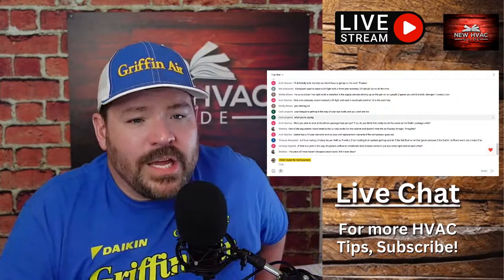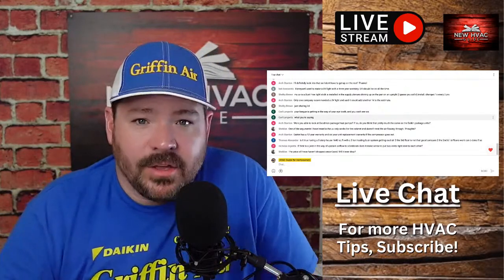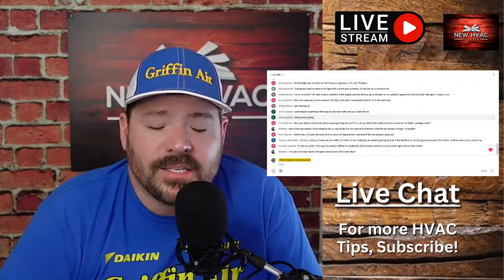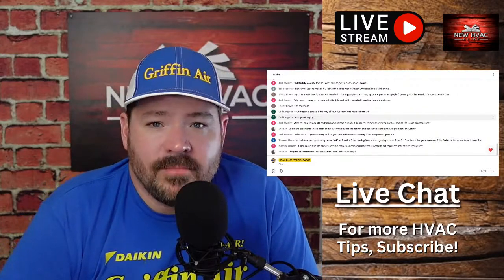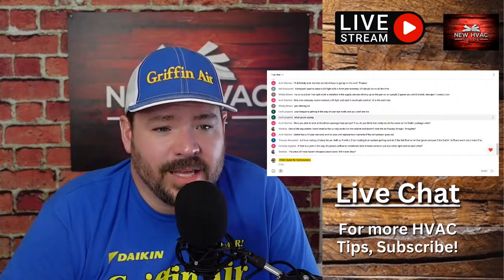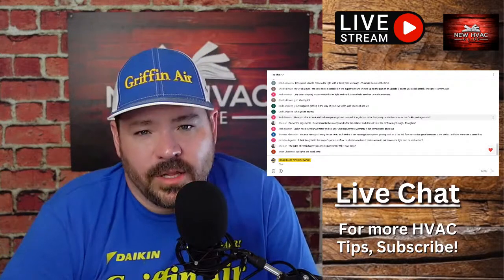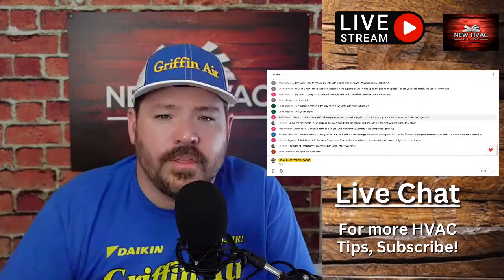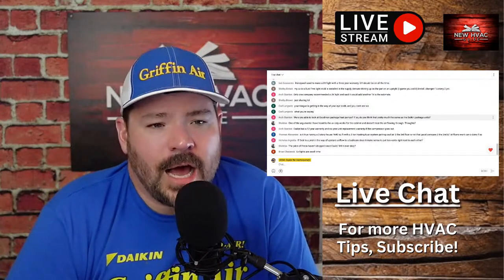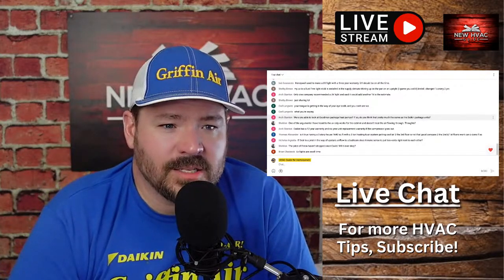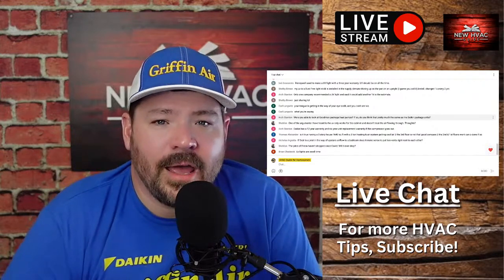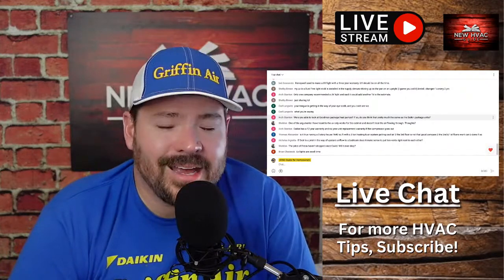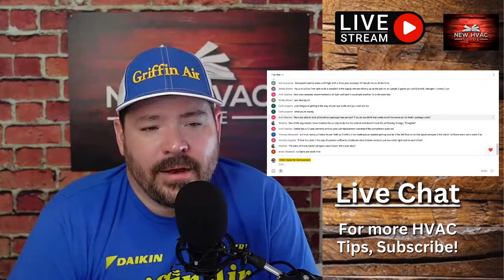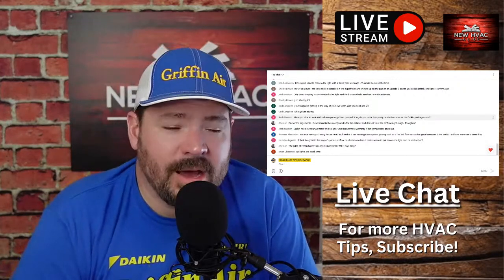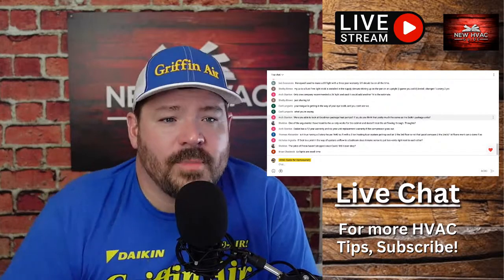So we talked, and I had him buy a UV light, and we installed it. I went back 6 months later and did maintenance on the system, cleaned it again, checked all the things we do on tune-ups, checked the refrigerant, cleaned the coils, treated the drains. I opened the system up expecting to see black buildup, and it blew me away. That coil was shiny as a nickel, a brand new nickel. From that day on, and that was 9 years ago or more, I was a believer.